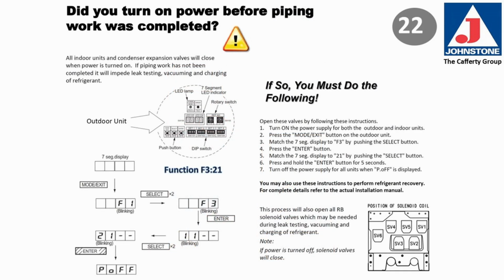Did someone turn power on to the system before the piping was completed? All of the indoor units and the condensing units have expansion valves that will close when the power is turned on. If the piping has not been completed, that will interfere with the leak testing, evacuation, and charging of the system. If that's happened, what do you do? You can open the valves by following these instructions.